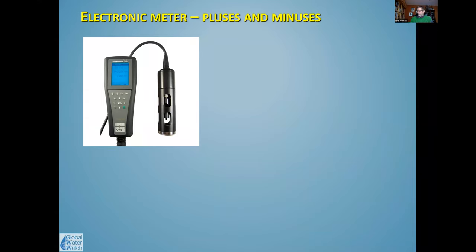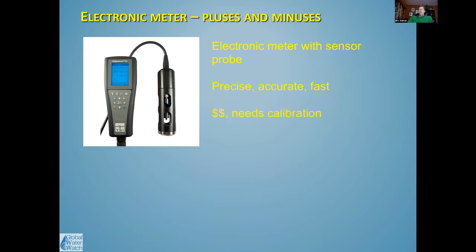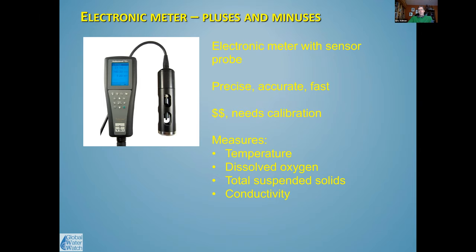With an electronic meter, the plus is that it's very quick and very accurate. The downside is that they're expensive — this type of probe costs a few thousand dollars by itself, needs calibration with specific calibration fluids every time you go out, and annual maintenance is pretty costly. You can get probes to measure a wide variety of variables, and they provide very detailed, accurate readings.